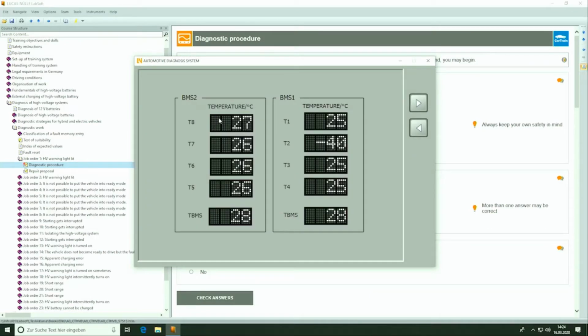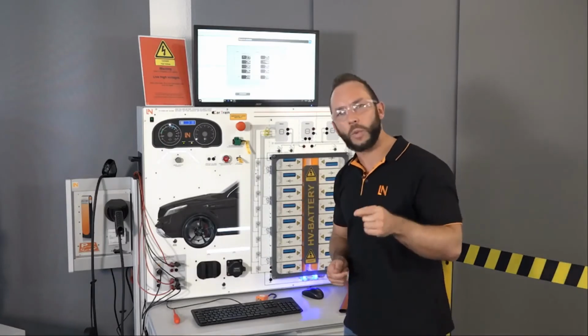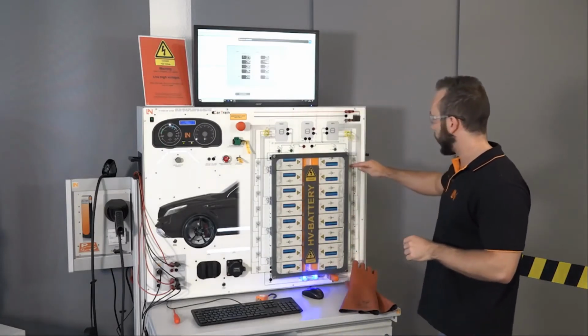What do we see here? We see now for each single temperature sensor the measured temperature. If we have a look at the monitor, we see on the left bank everything is fine. We read around 27 degrees. On the right-hand side, we suddenly see that temperature sensor 2 shows a temperature of minus 40 degrees. What does it mean for us now? We are all aware that this is not the normal temperature. So at first, let's locate where the sensor is. We have here T1, T2. That means here we have the temperature sensor, which is obviously faulty.